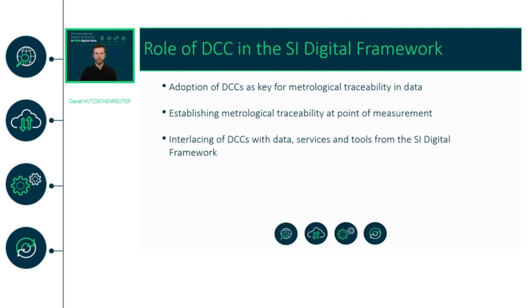New kinds of measuring equipment will allow storing calibration data on the device, allowing this data to enhance measurement results. Thus, CIPM endorses the DCC for metrological traceability at the point of measurement.